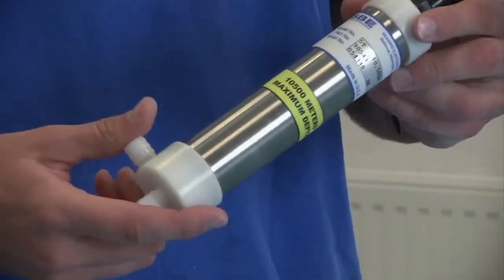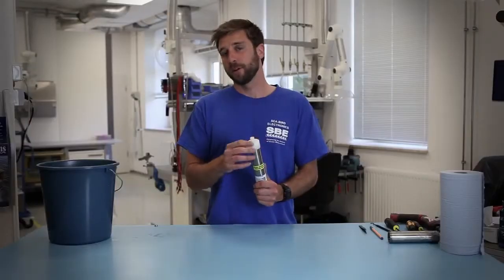One of the more important concepts of this is to check the impeller and impeller shaft of the pump. This is done by removing the impeller end cap here. It will just unscrew and you can see the impeller should be free spinning.